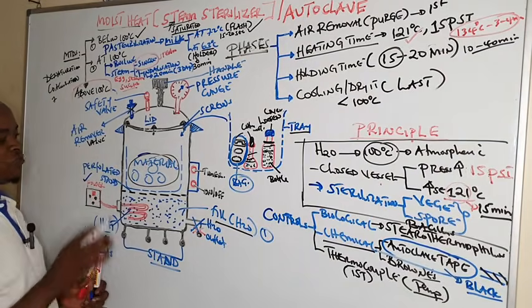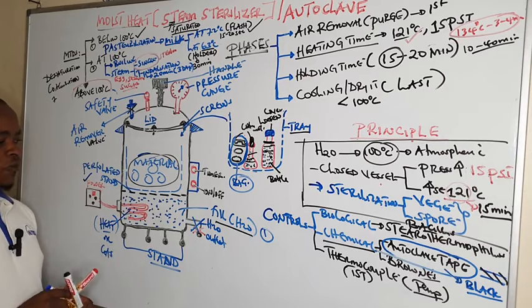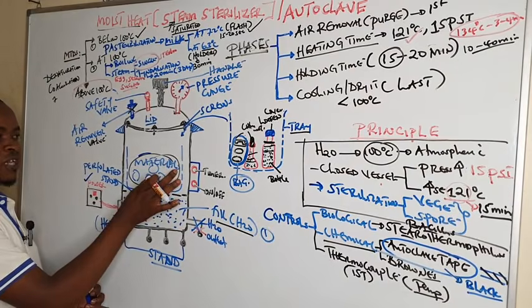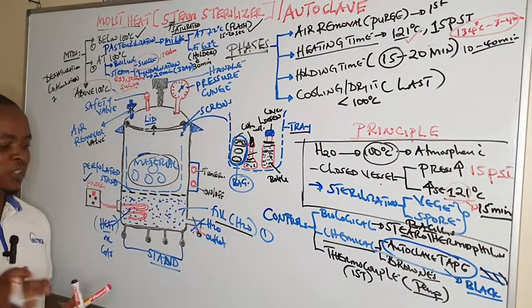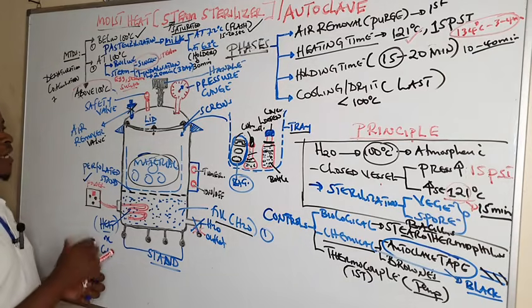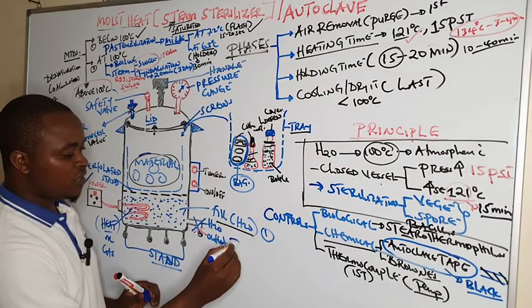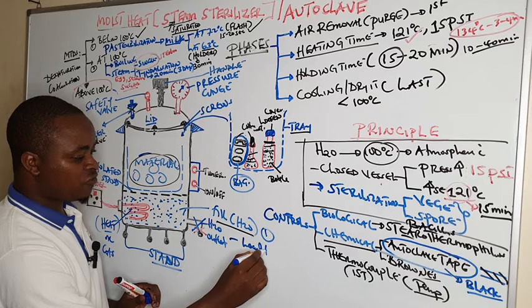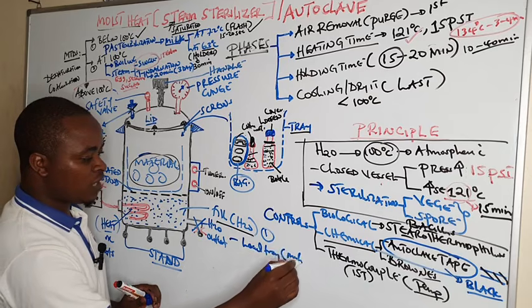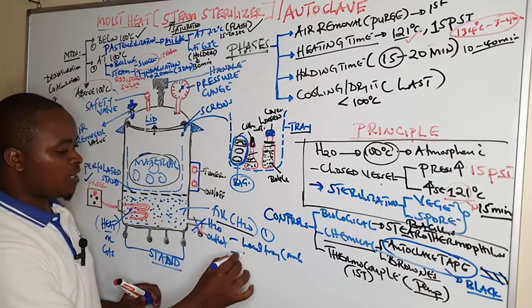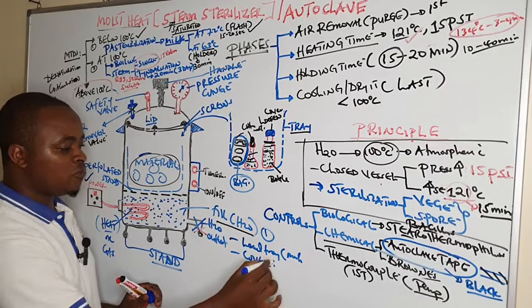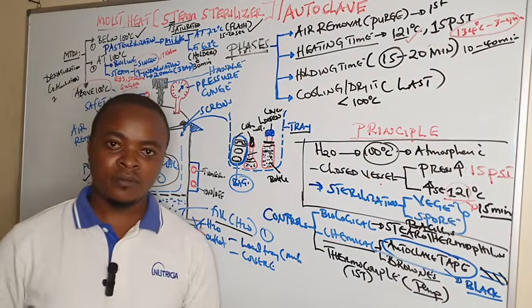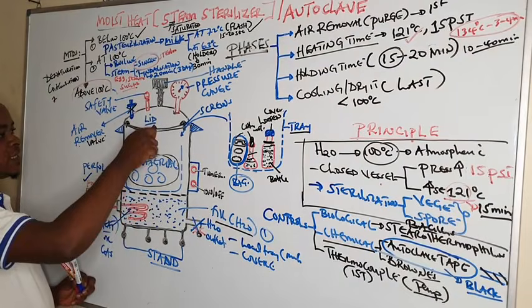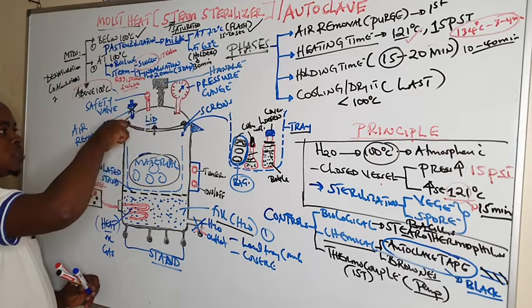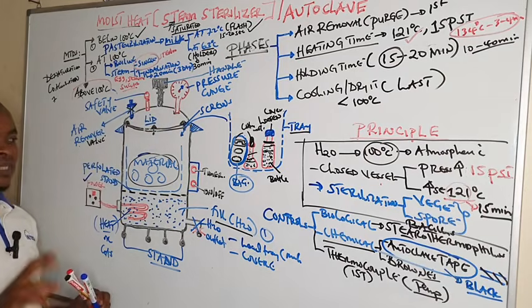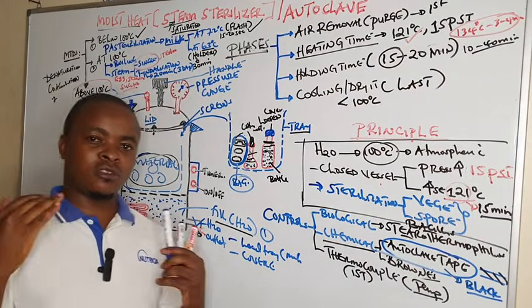So after putting the tray in the autoclave, we have filled it with water, and we have loaded the tray which has the materials to be autoclaved. After loading, we now come and cover tightly, or we can say we secure the lid. And how do we secure the lid? By tightly closing the screws. The screws must be tightly closed so that we don't allow any steam to escape.